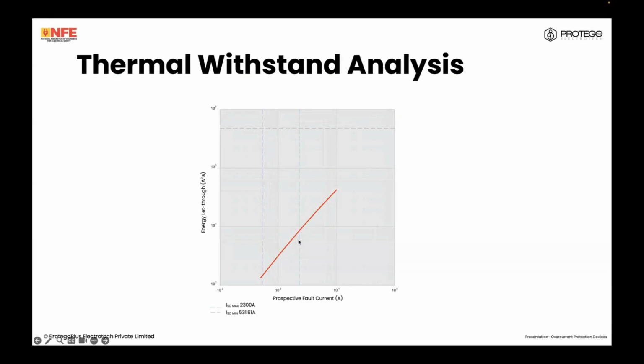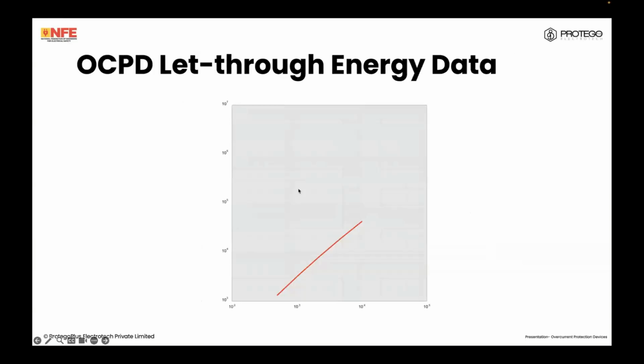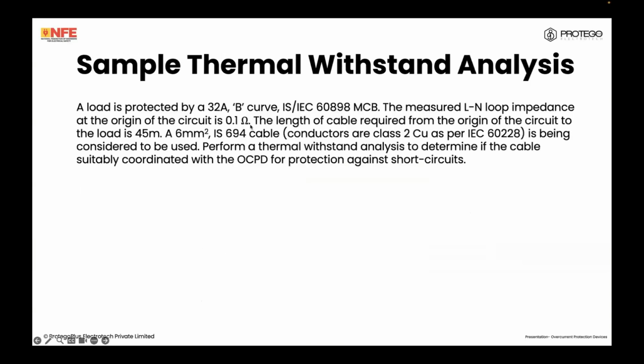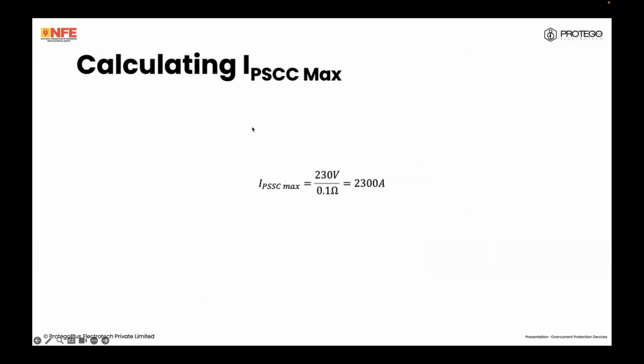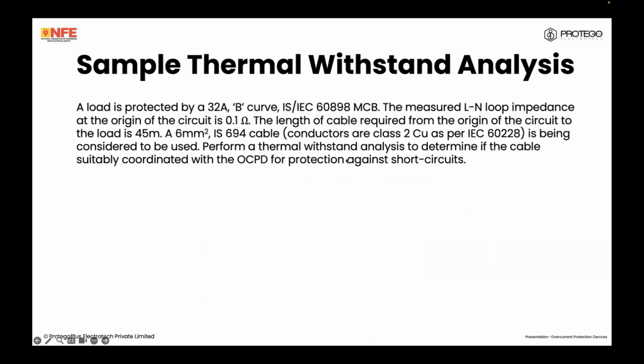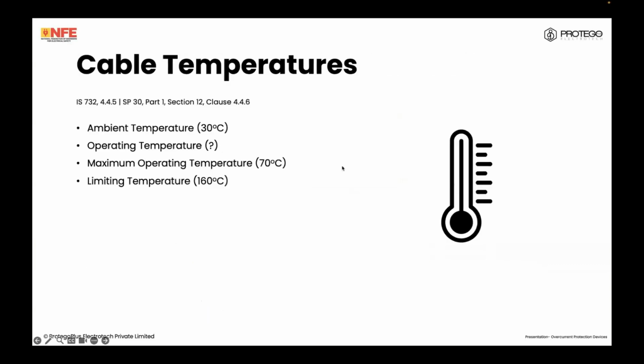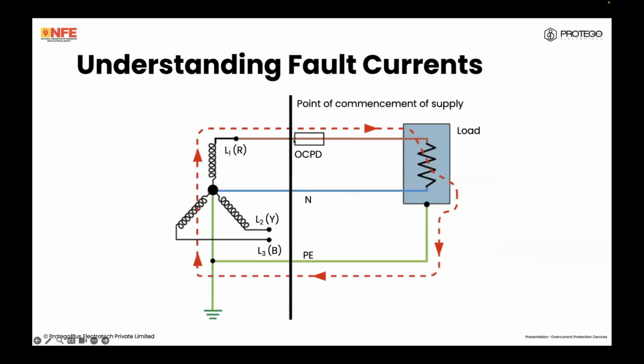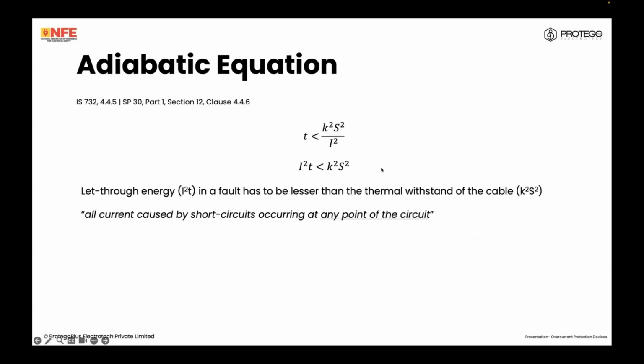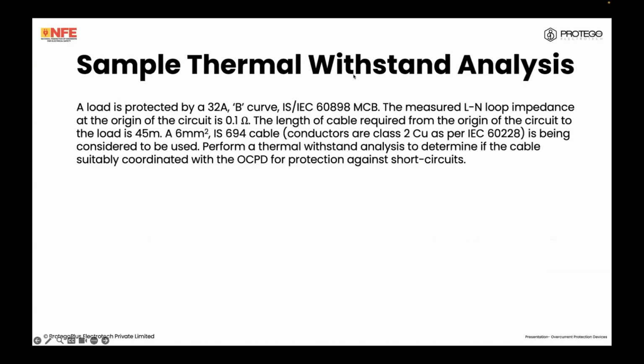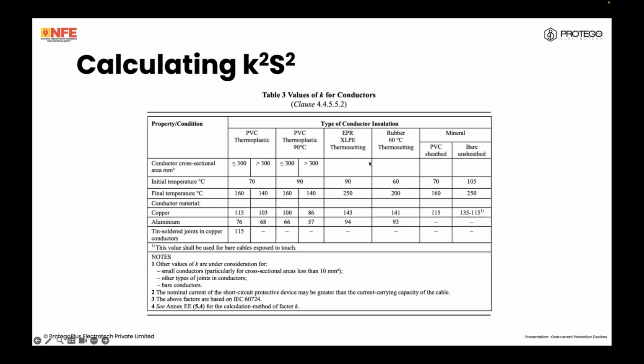Now remember, I ran this calculation for line to neutral loop impedance and short circuit. However, for earth faults of negligible impedance, this also has to be run, given the earth fault loop impedance at the point of commencement of supply, adding the resistance of the wires, and calculating the earth fault loop impedance at the extremity, and then rerunning this analysis. The process is exactly the same, just a different calculation is required.